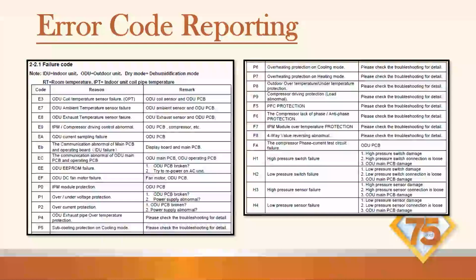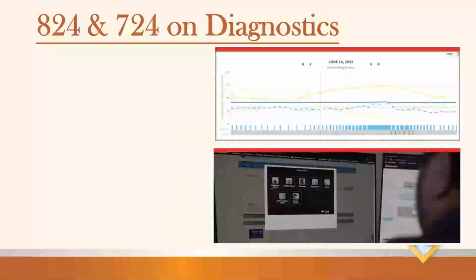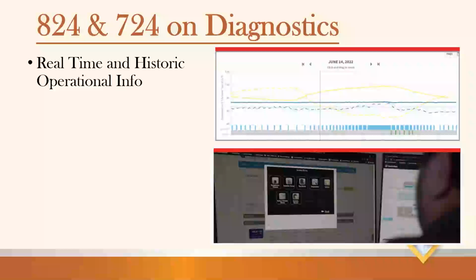Error codes. Again, that'll be in the service facts and installation manual. Give us a call at Tech Services, we can help you navigate those error codes. If you have an 824 or 724, you can take advantage of online diagnostics. Again, we can't see all the sensors like we can on a link system or true variable speed, but we can still see operation and runtime, and we still get some information in that diagnostics that's critical. We might be able to tell you something before you go out to the job.